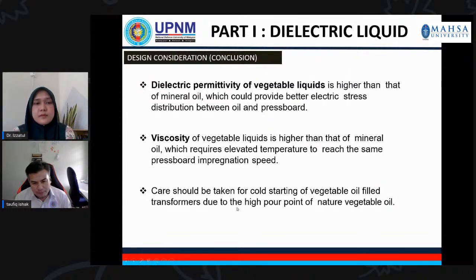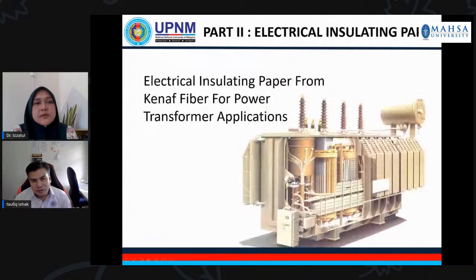In terms of cold starting, when using this in a cold country, we should take care when using a vegetable oil filled transformer, due to the high pour point of the vegetable oil. So you need to have a special requirement for it to be used in cold weather. All right. This is the first part, and then we go for the second part. It's going to be quick.